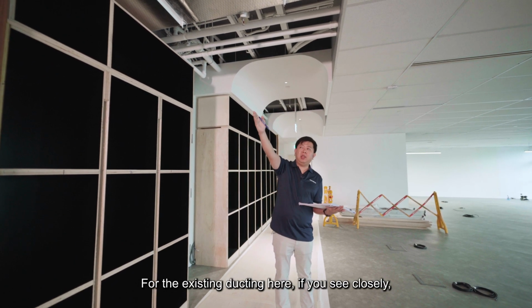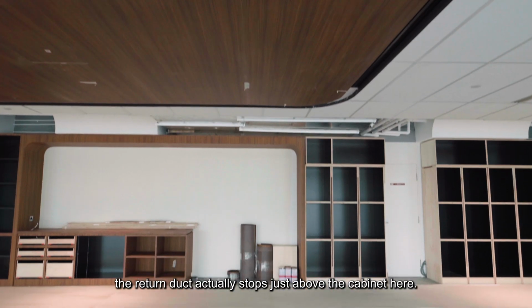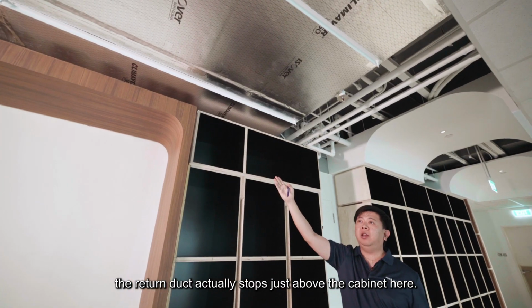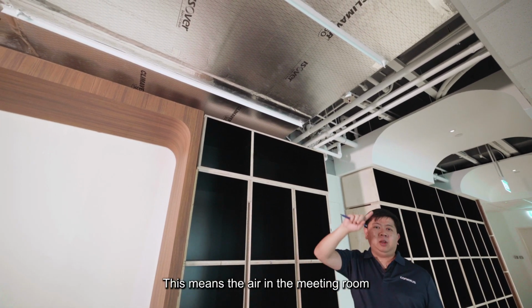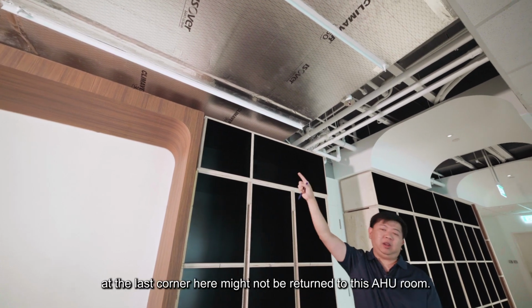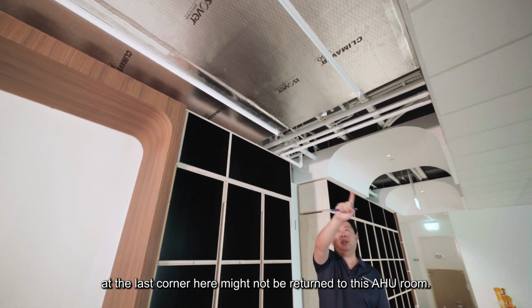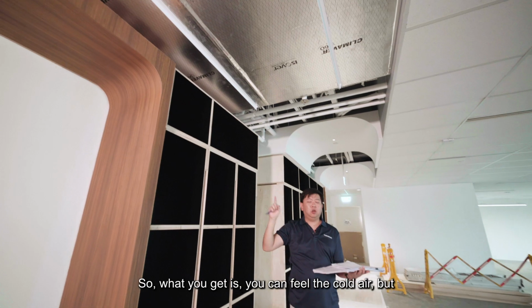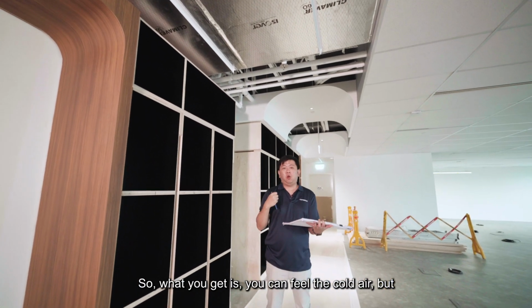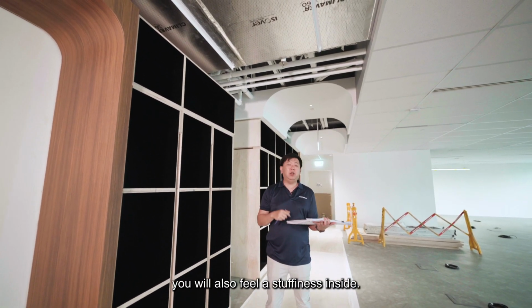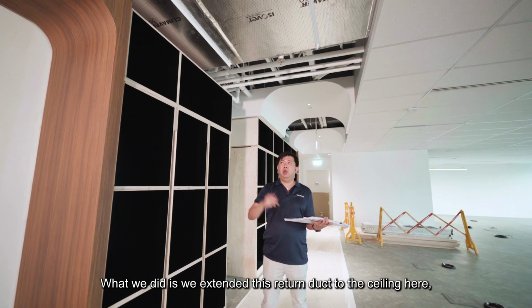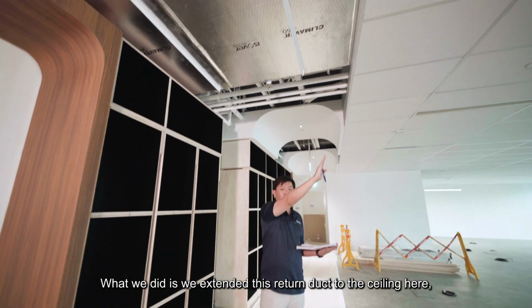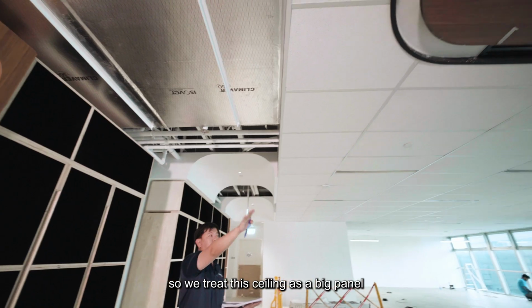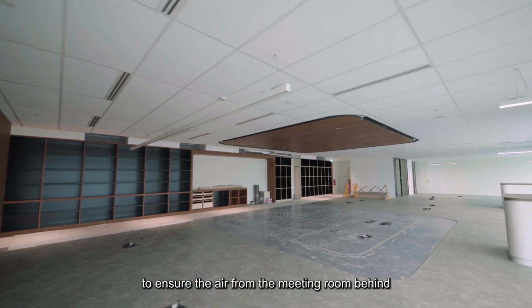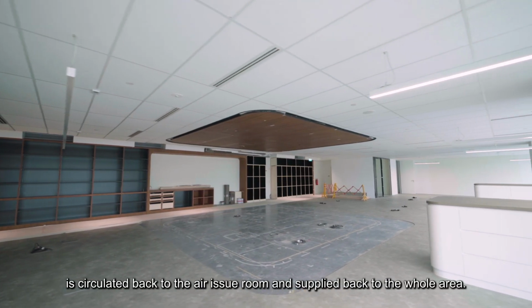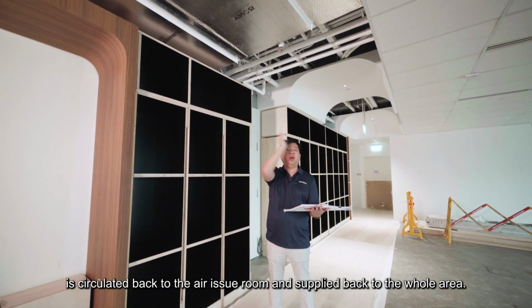At the existing ducting here, the return duct actually just stops above the cabinet. That means the air in the meeting room at the last corner might not be returned to the AHU room — so you feel the cold air, but also a stuffiness inside. So what we did was extend this return duct to the ceiling, treating the ceiling as a big plenum, to ensure the air from the meeting room behind is circulated back to the AHU room and supplied back to the whole area.